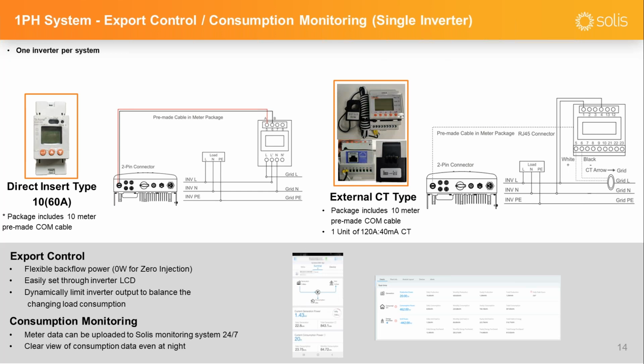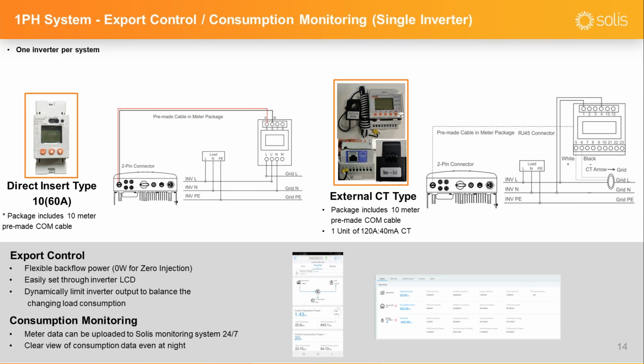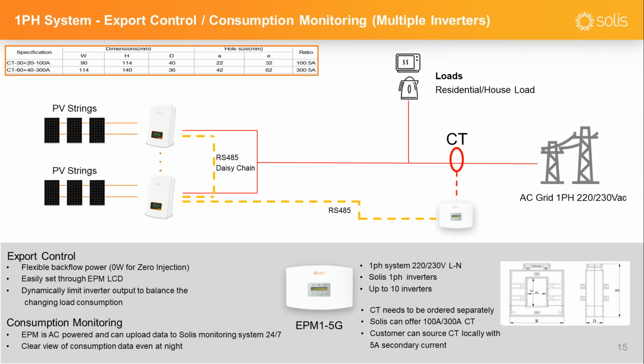And previously we talked about one inverter per system. If you have multiple single phase inverters in one system and you want to do export power control or consumption monitoring, then we can also offer an EPM box, or EPM 5G. This is the extra control box, and all the inverters will be daisy chained through RS-485 cables and then linked to the EPM box. An EPM box should be installed at the grid connection point of your system and connected to the CT to do the current measurement at that point. This device can support Solis single phase inverters, no matter what models they are. So you can have one 2K inverter and another 5K inverter, and they can all communicate with the EPM 5G. Up to 10 inverters can be connected in the system.